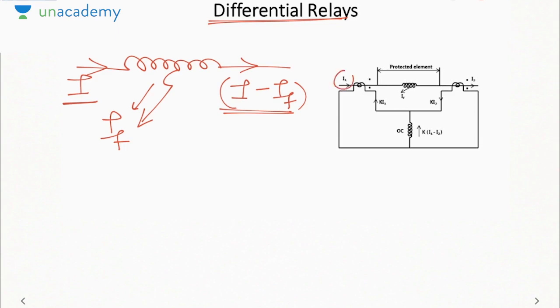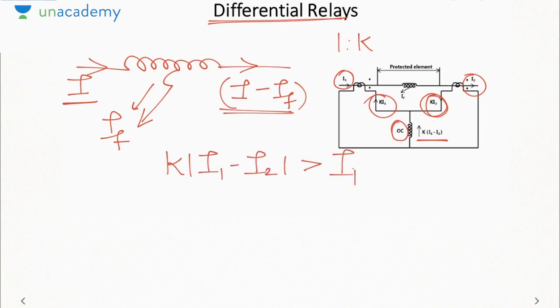Now suppose the current here is I1, the current here is I2. If the current transformer ratio is 1:k, that means 1 ampere current is converted to k, so I1 will be converted to kI1 and I2 will be converted to kI2. This OC represents the relay operating coil, that is, the operating coil of the overcurrent relay. So by KCL, what is the current? k into I1 minus I2. Now for overcurrent relay operation, k into mod I1 minus I2 must be greater than I pickup. Whenever the current through the operating coil is greater than I pickup, the relay will operate.